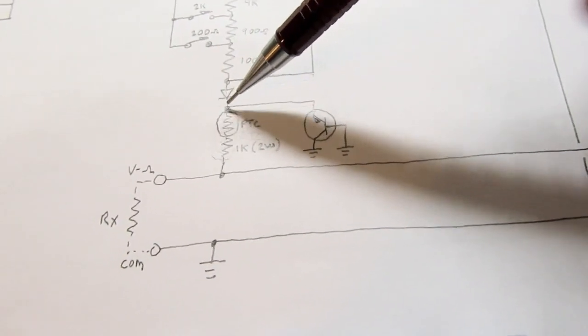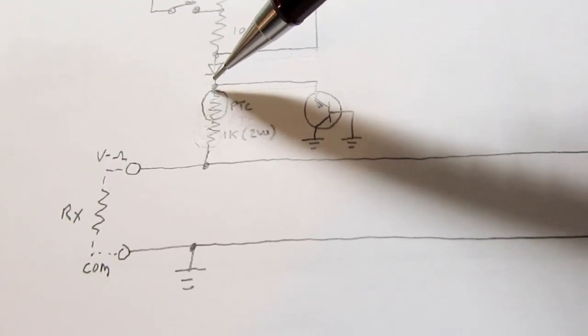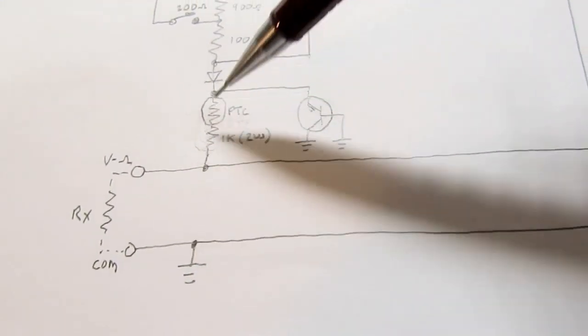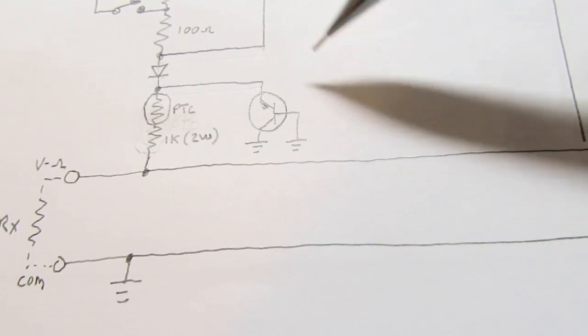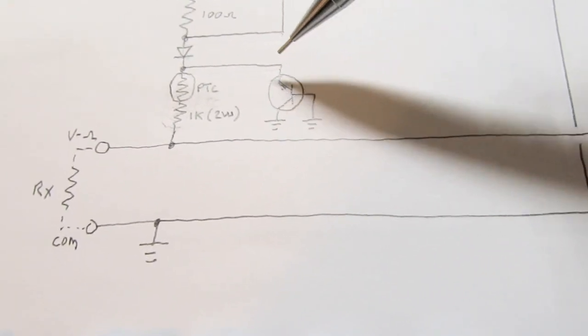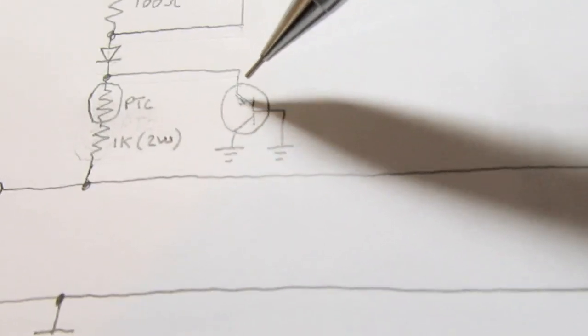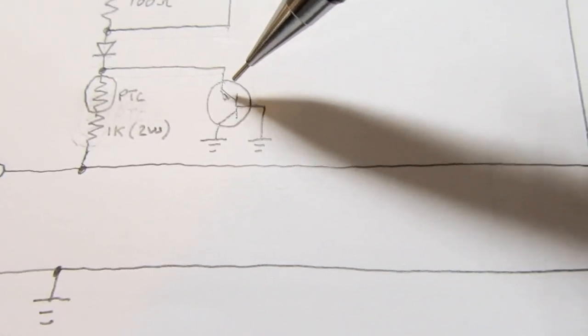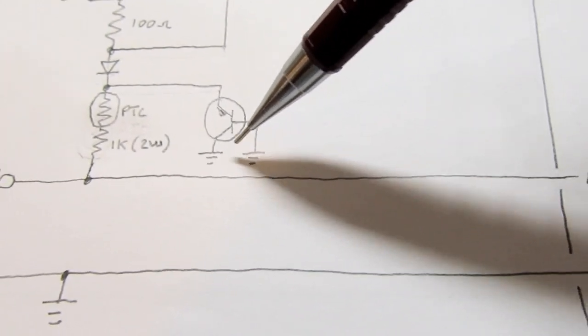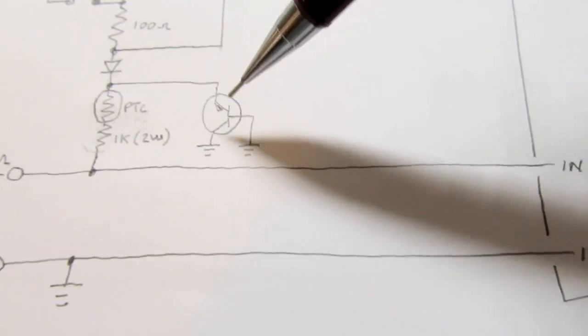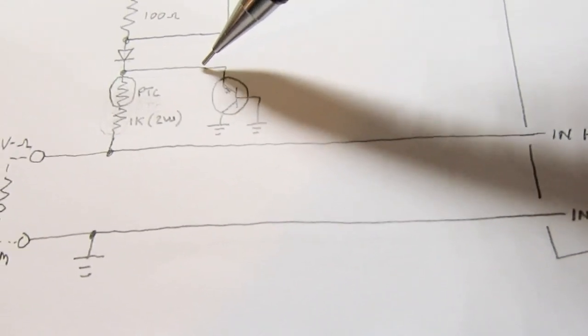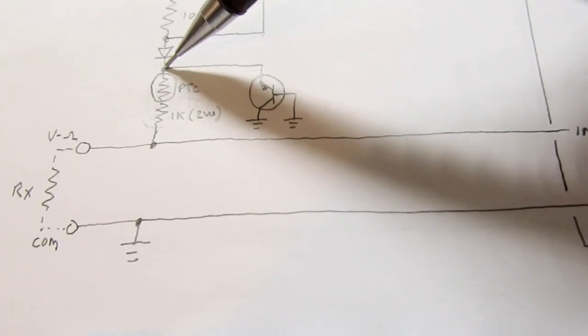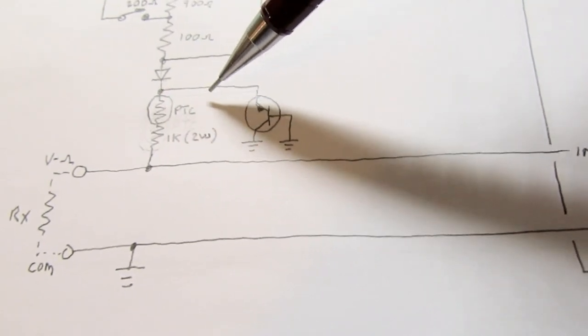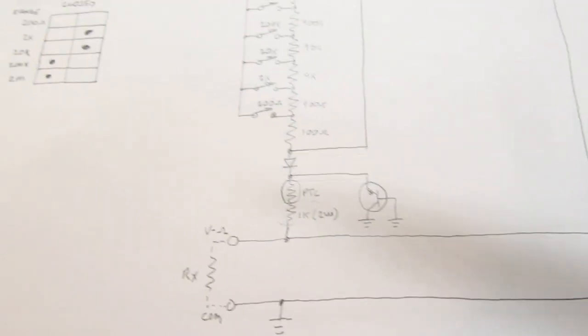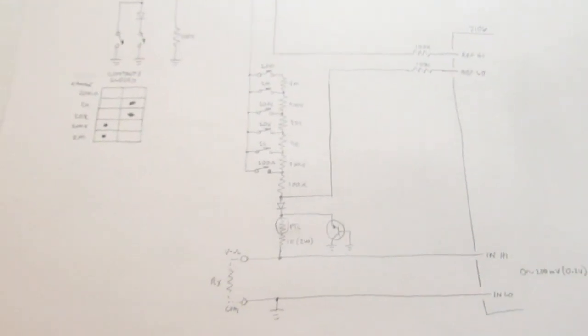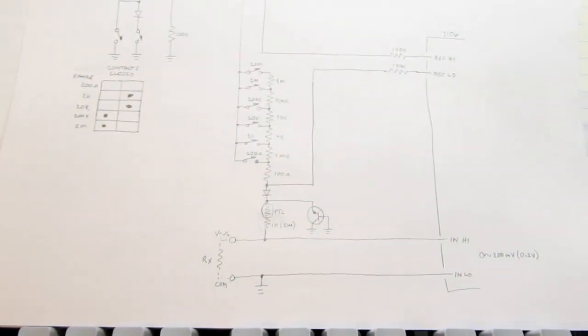And also, if you develop too high a voltage at this point relative to circuit common, then this reverse connected NPN transistor starts conducting. It conducts in reverse, but a standard bipolar transistor connected in reverse like this, with its base connected as this one is, behaves like a Zener diode. So this is basically just a poor man's Zener diode. So again, it clamps the voltage here to no more than a certain amount. So that's another safety to prevent the meter from being damaged if you do something dumb with your test lead connections.